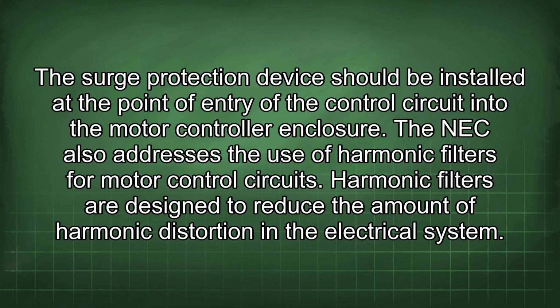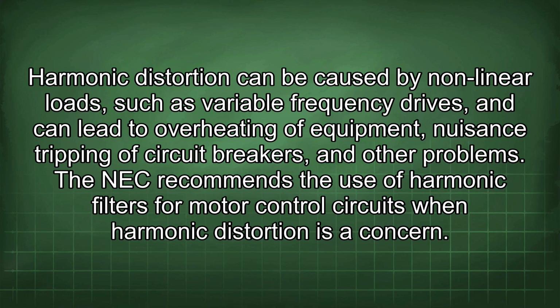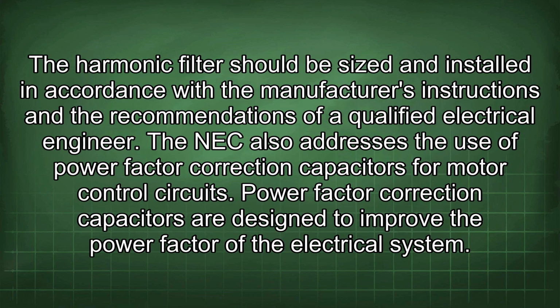The NEC also addresses the use of harmonic filters for motor control circuits. Harmonic filters are designed to reduce the amount of harmonic distortion in the electrical system. Harmonic distortion can be caused by nonlinear loads such as variable frequency drives, and can lead to overheating of equipment, nuisance tripping of circuit breakers, and other problems. The NEC recommends the use of harmonic filters for motor control circuits when harmonic distortion is a concern. The harmonic filter should be sized and installed in accordance with the manufacturer's instructions and the recommendations of a qualified electrical engineer.